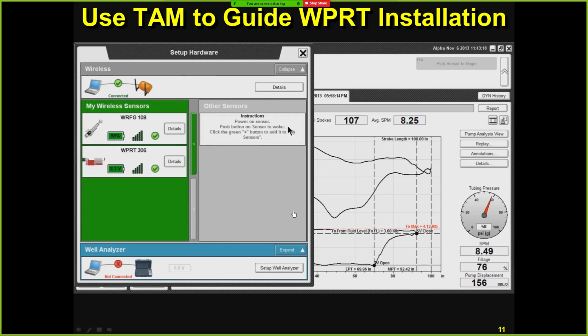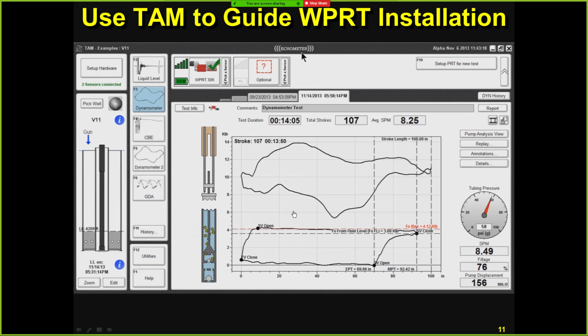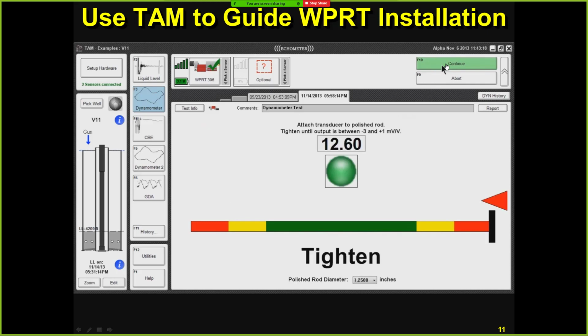And so we selected the wireless PRT. And we're going to go to acquire data and set the PRT up. And so I'm going to click on this. We've got it selected to acquire data, dynamometer data in TAM. And I'm going to come over here and click on this setup button. And then the same thing will happen, except now I'll be looking at the screen. And the screen will show that the output of the PRT is close to 15. And then as you gradually tighten it, this number is going to drop.